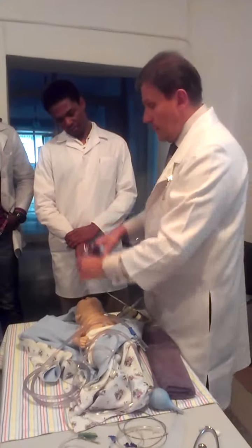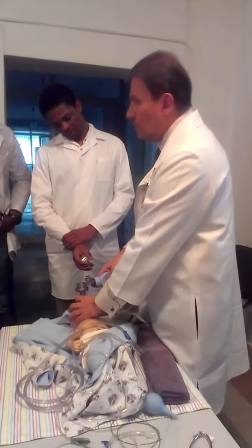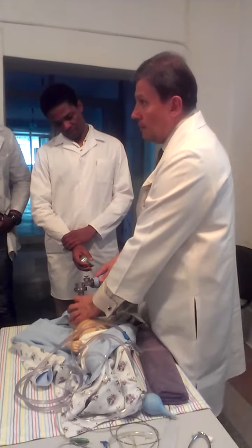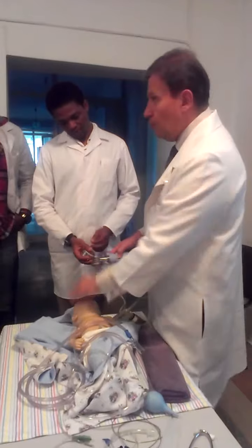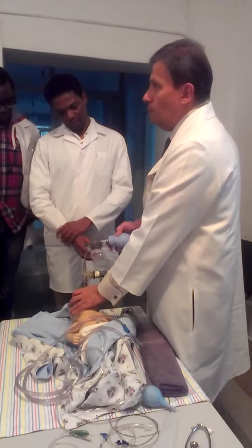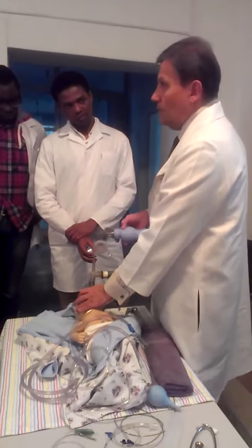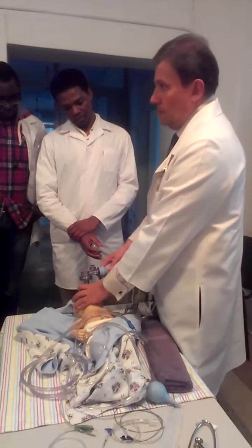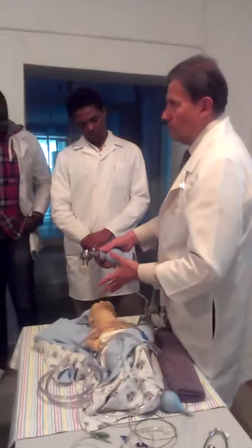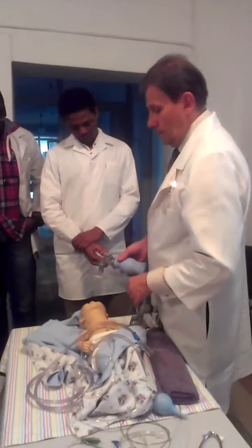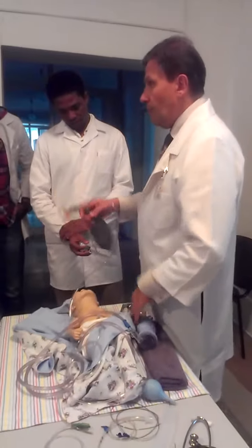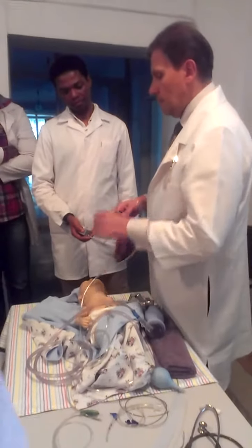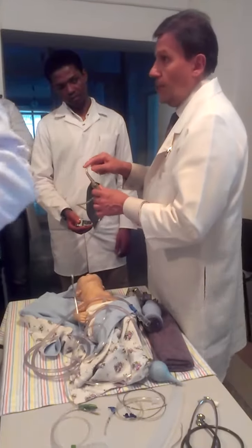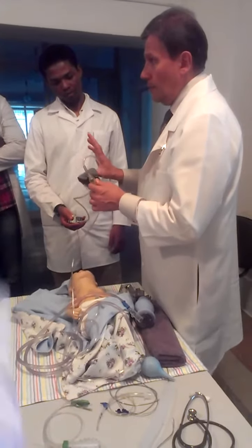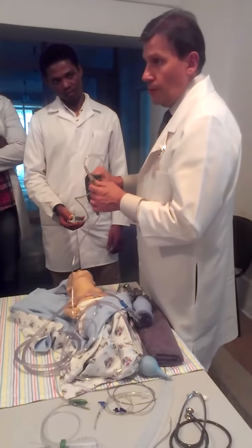So that is why with this bag, as soon as you put mask like this, you should start ventilation. Otherwise, you are creating asphyxia. With this bag, you can put and have CPAP. Baby is breathing, and there is a flow, there is a gas exchange. With this, there is not. And if you put like this, no oxygen. Okay? So, pressure which you will create in patient's lung will depend on the flow. The higher the flow, the higher the pressure. And second point, your strength, your power with which you will squeeze the bag.